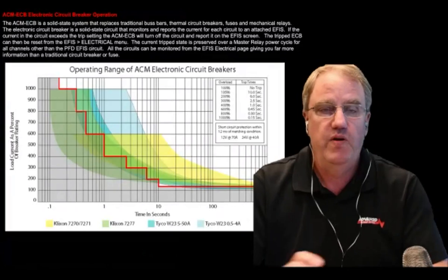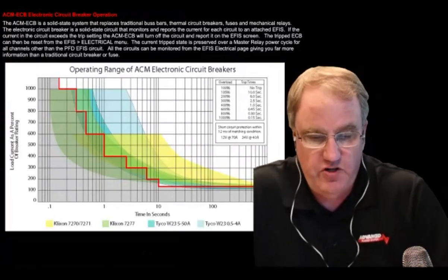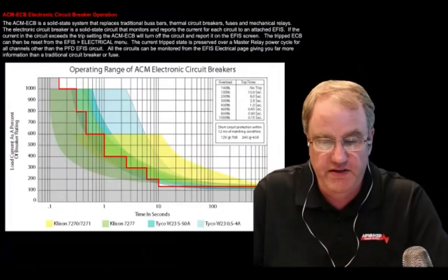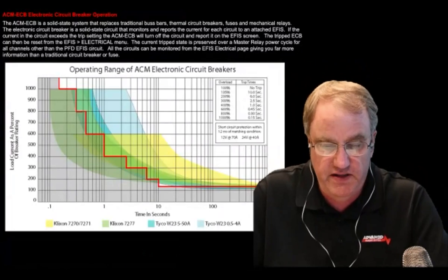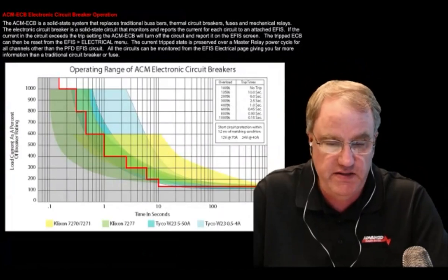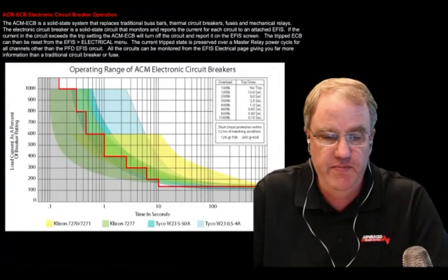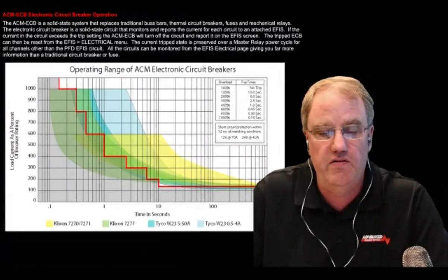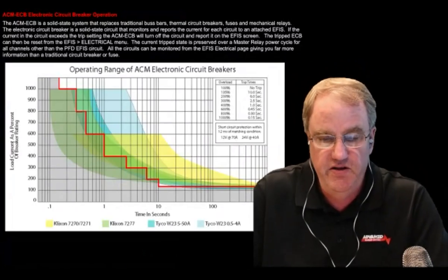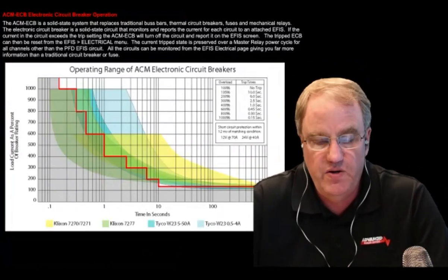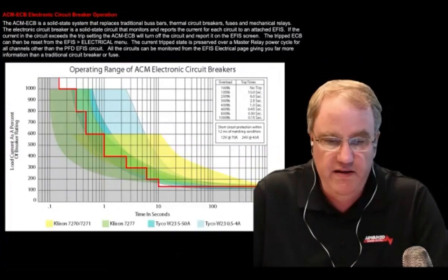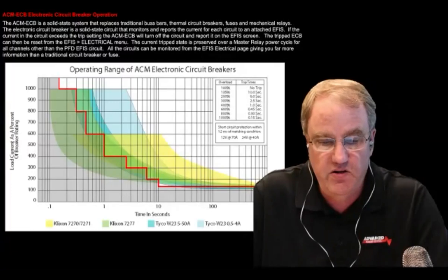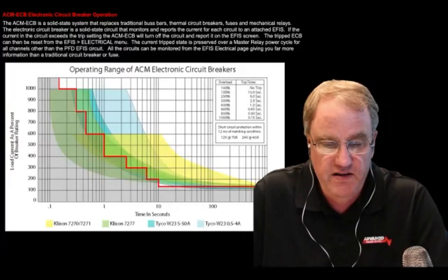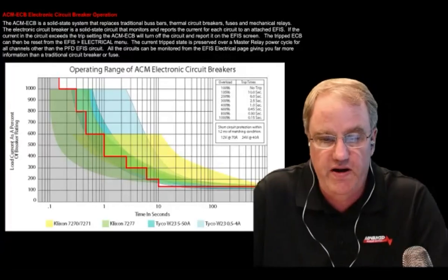We get a lot of questions on how a circuit breaker trips. So this shows all the traditional circuit breakers, the Klixons and the Tyco circuit breakers, and this is a trip curve. This is the time in seconds and the load current rating up on the left side, so you can see where each different circuit breaker trips. The red line is what an ACM does. We program this in software, looking at time and rate, and that's where our circuit breaker actually trips.